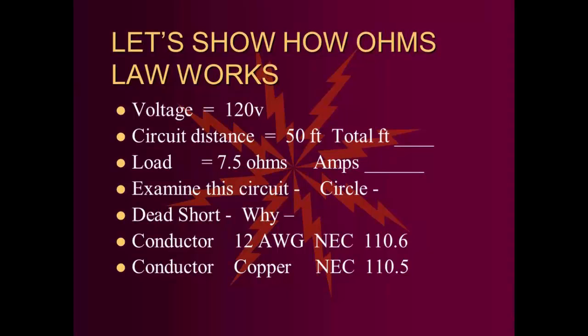The voltage is 120 volts. The circuit distance we're going to say is 50 feet. Now if you have a circuit that's 50 feet away and there's 2 wires, what's the total footage? 50 foot? No, it's 100 feet. It's got to go down 50 and back 50, correct? So it's 100 feet. We're going to say the load is 7.5 ohms. What is the amperage, or what are the amps that that's drawing?